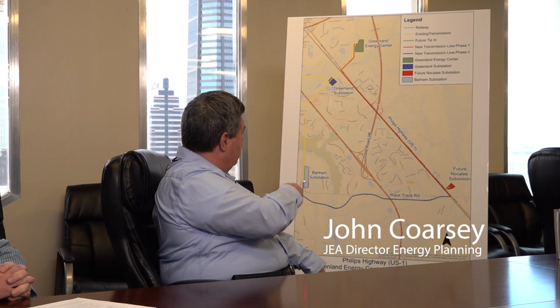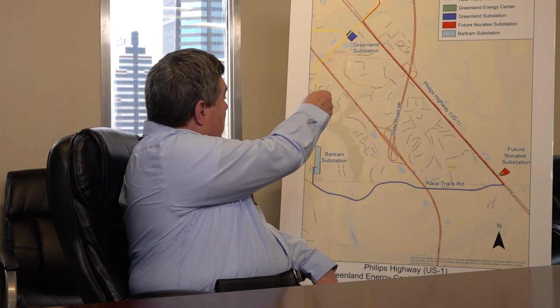Two issues with this. The first is the existing transmission line. It's what we call H-frame construction: two poles, 30 to 40 feet apart, with a crossbar across the top, and the conductors arranged very wide. It takes up a big part of the right-of-way. There's not enough room to build a second transmission line with the original circuit in that configuration. So the original circuit would have to be rebuilt to monopole, single-pole type construction, which is the type we're proposing here, and then a second line built.